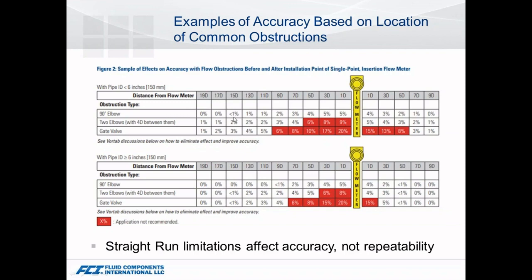One area you can look at is: what is the obstruction, how many diameters is it from my meter location, and what impact does it have on accuracy? Looking at this chart — elbows up and down, two elbows in series, a gate valve — the red doesn't indicate a bad application; the red just indicates an inaccuracy greater than 5%. So evaluating impact on straight run, the number one question is: what accuracy are you trying to achieve, and what kind of solutions do we take to get there? Before you can take that next step, you really have to understand what inaccuracies are being introduced.